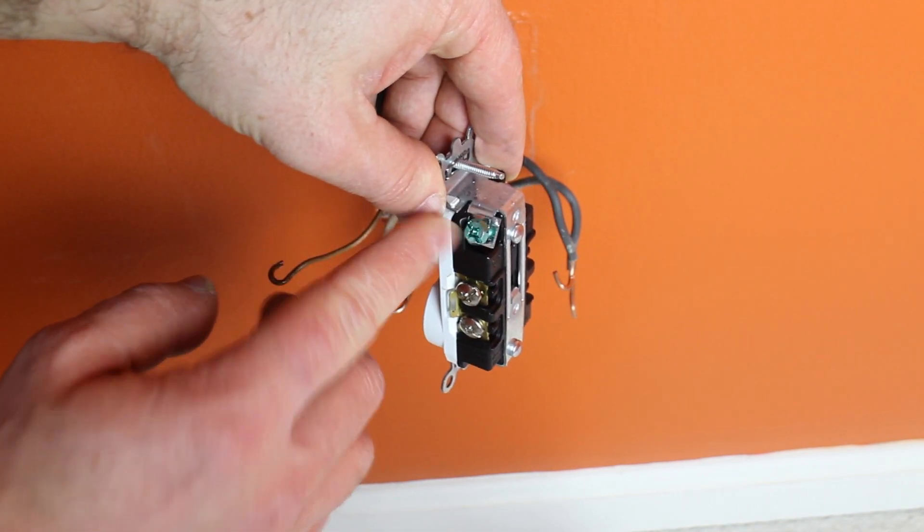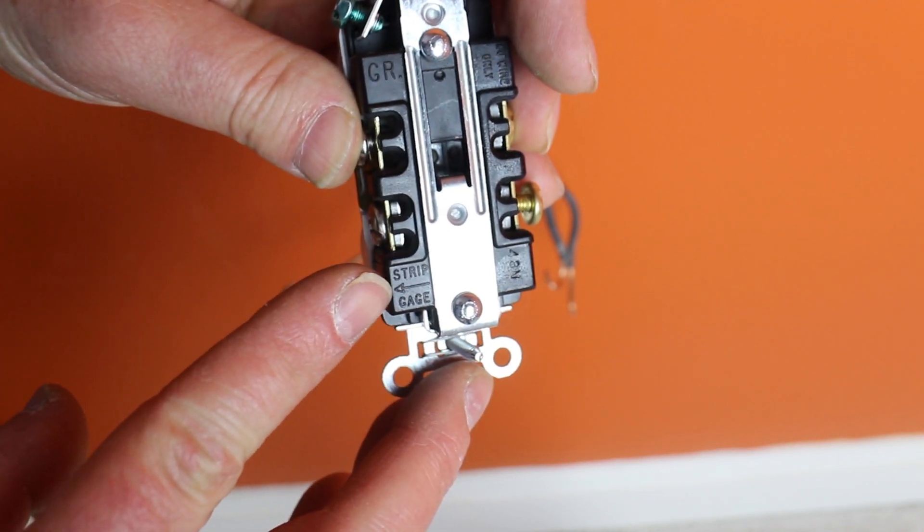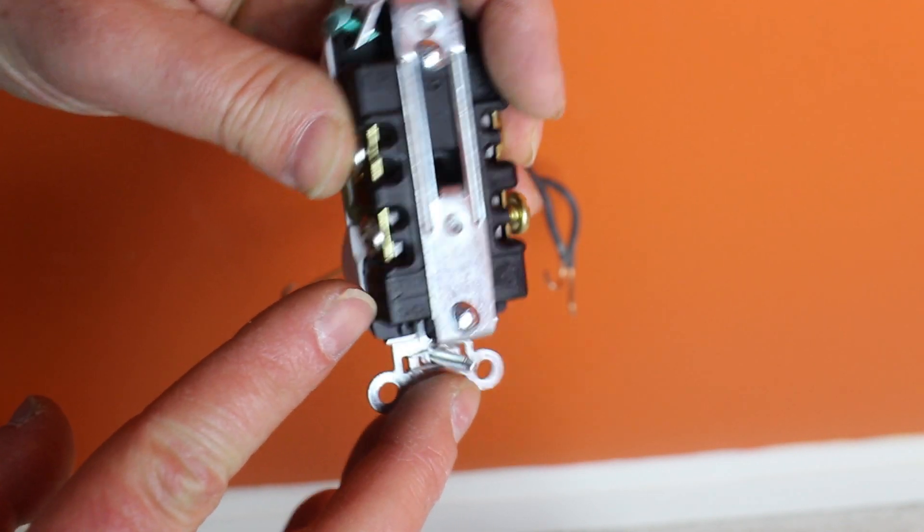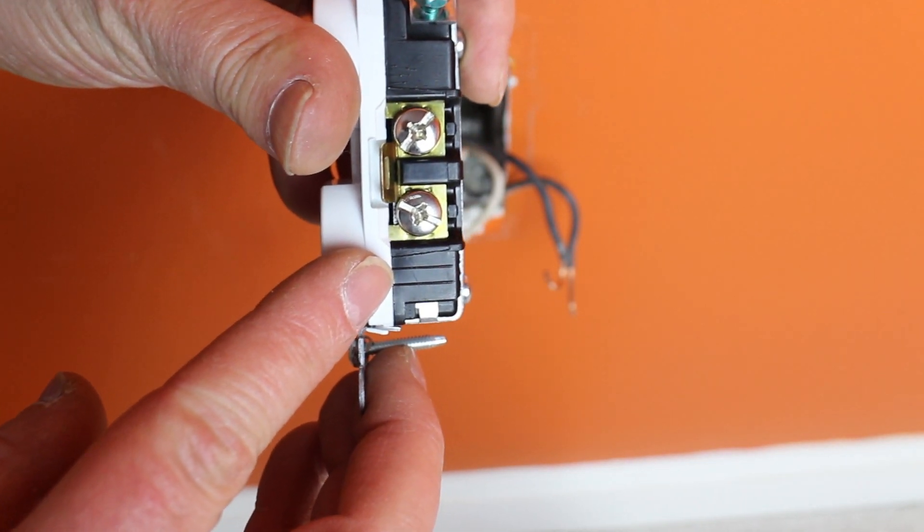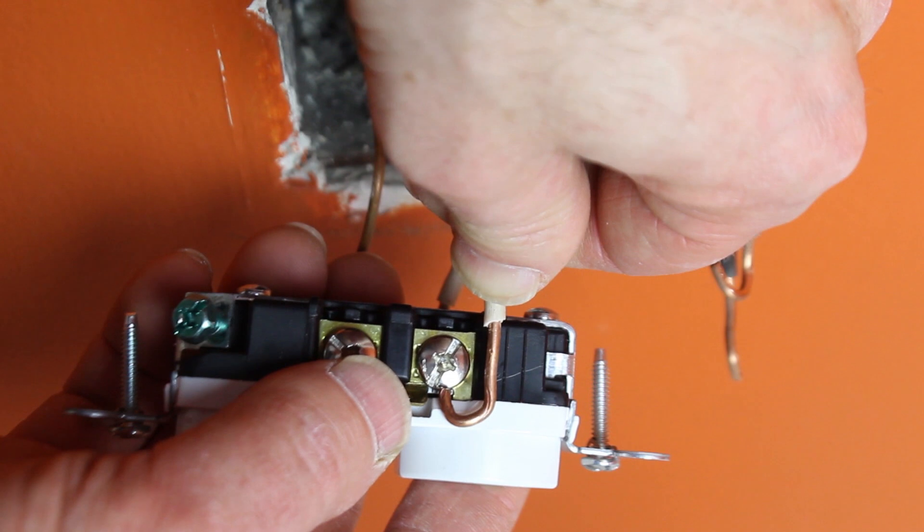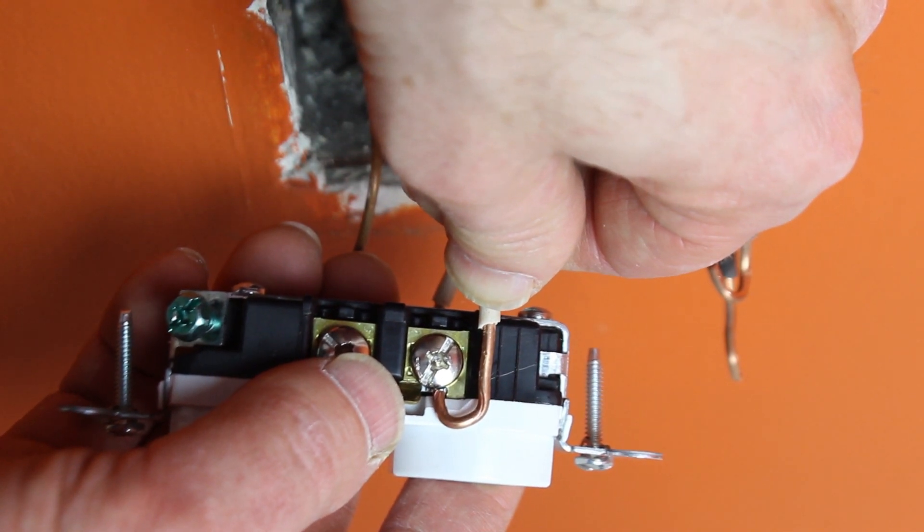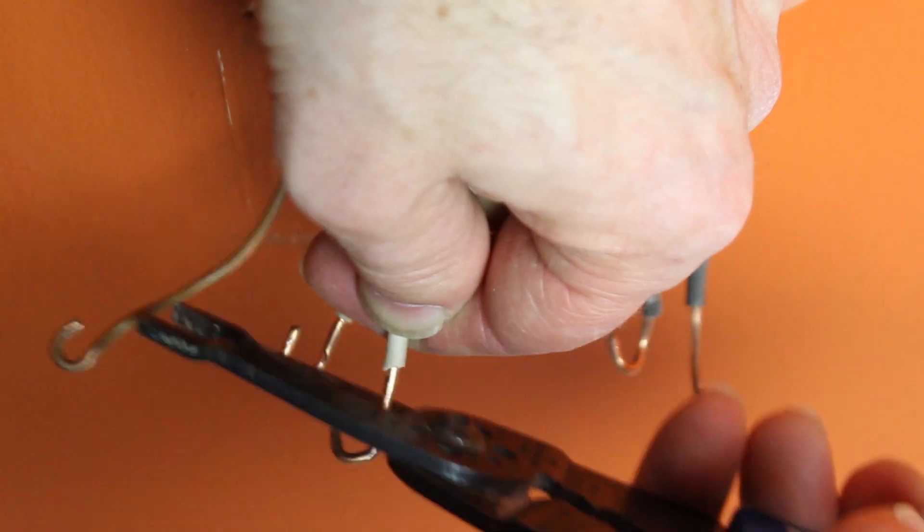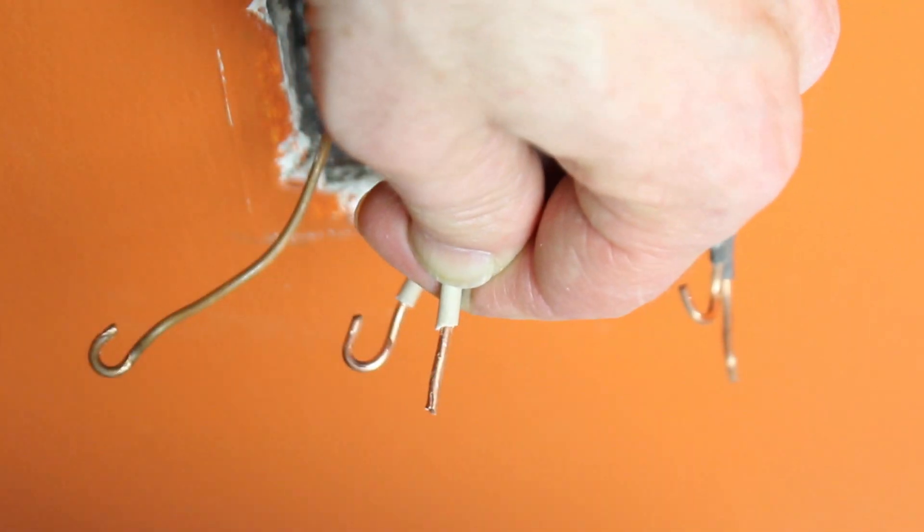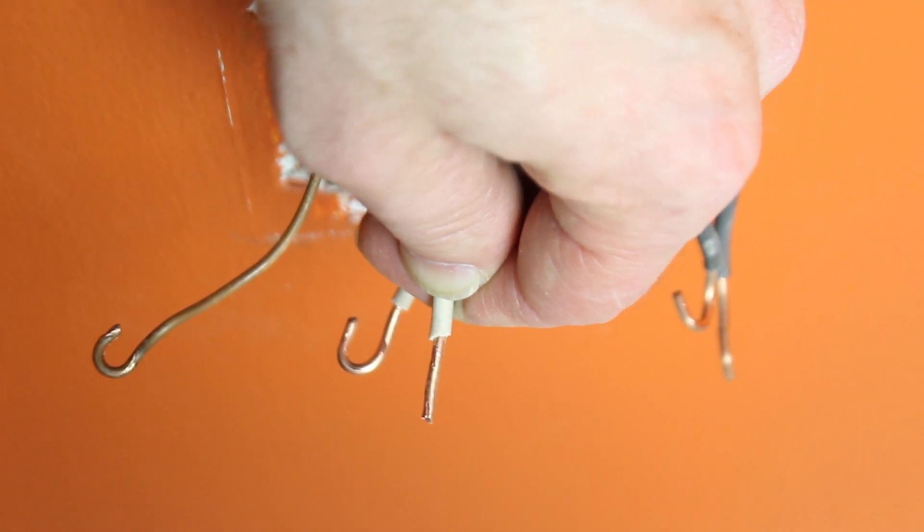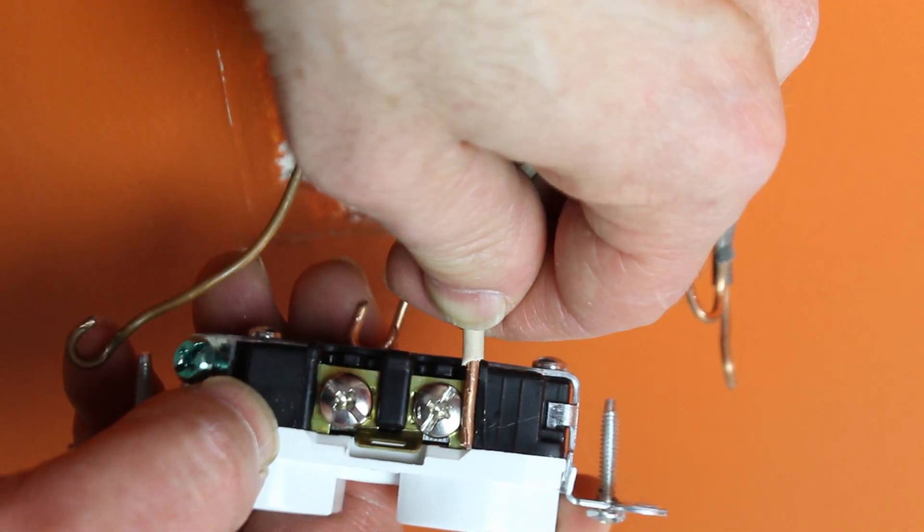Now, in this case, I wanted to show you there's a little strip gauge on the side of the outlet. This is really handy because what you can do is you can put your wires up against that strip gauge, and you can cut them the size or you can strip the insulation off according to the gauge. Once you do that for one wire, you can simply just put the wire up against all the other ones and strip off the appropriate amount of insulation.